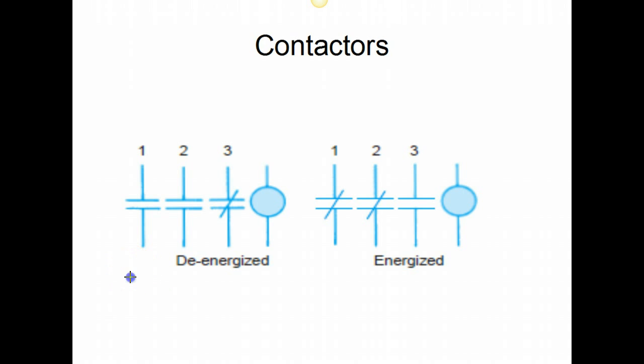In a schematic diagram, a contactor or relay is always depicted in the de-energized state, meaning there's no voltage applied to the coil itself. And these are the positions that the contact should be in if it's not damaged and it's working properly. So just remember, when you look at a schematic diagram, the contactors are shown in the de-energized position.